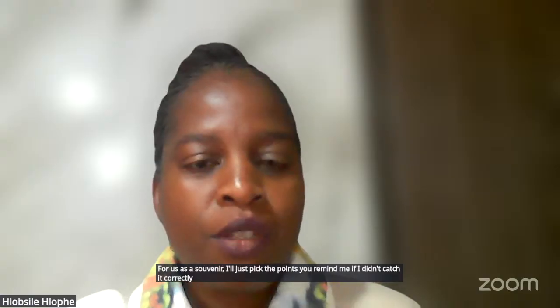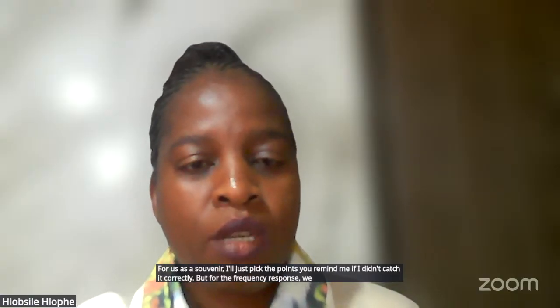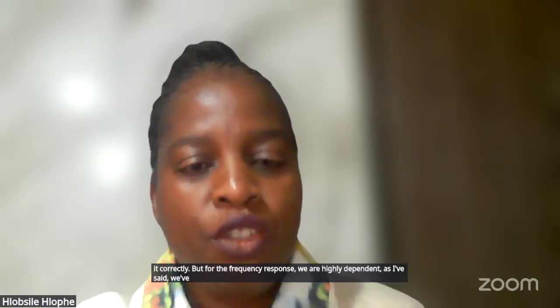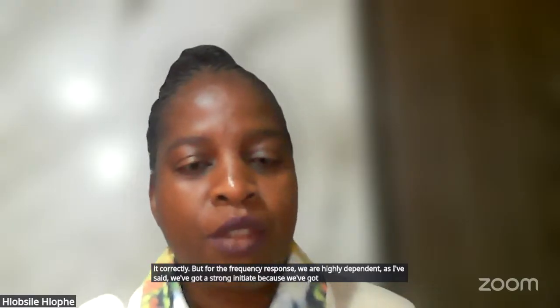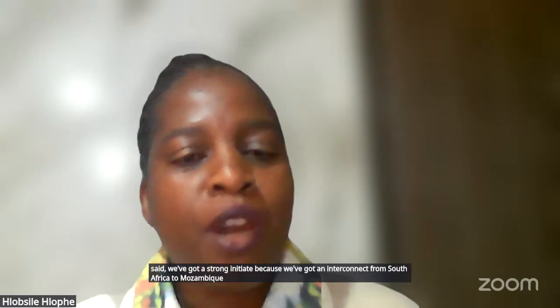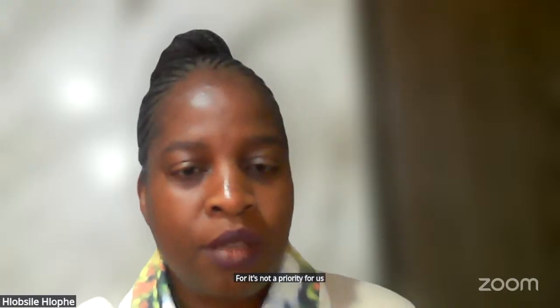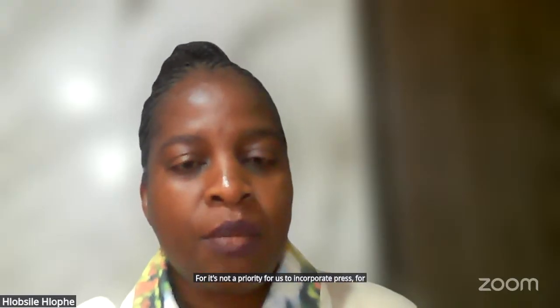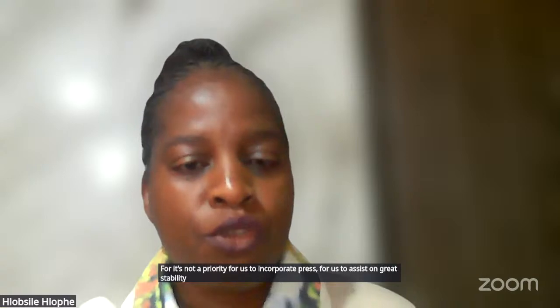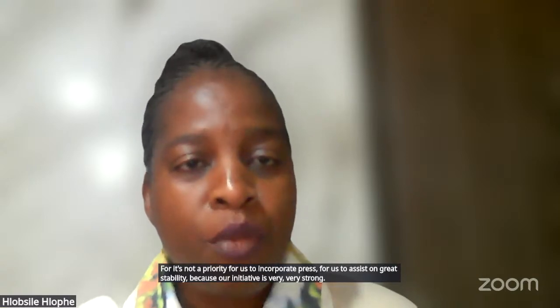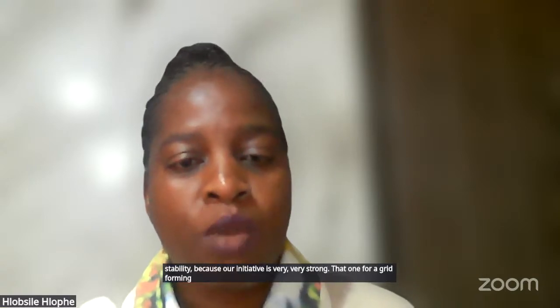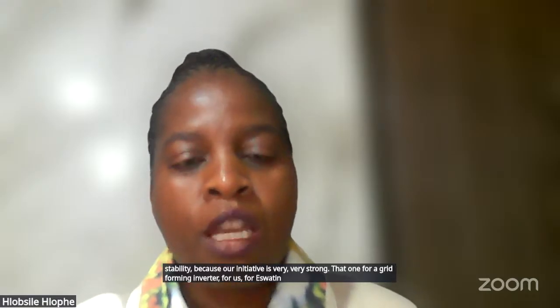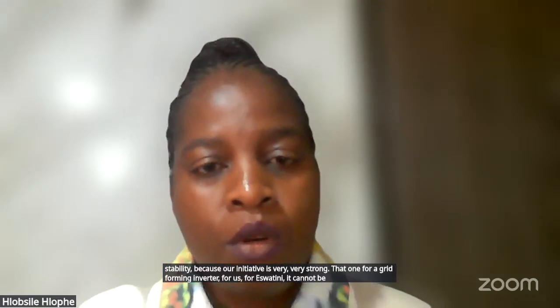For the frequency response, we are highly dependent—as I've said, we've got strong inertia because we have an interconnector from South Africa to Mozambique. It's not a priority for us to incorporate BESS to assist with grid stability, because our inertia is very strong. So a grid forming inverter cannot be a priority for Eswatini right now.